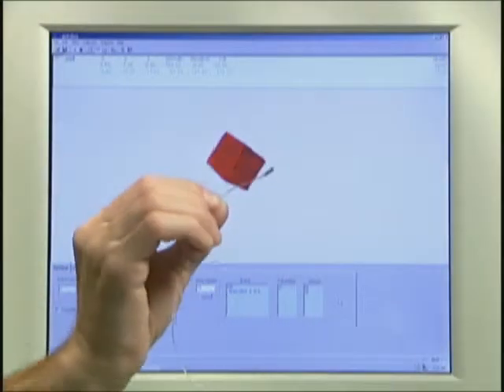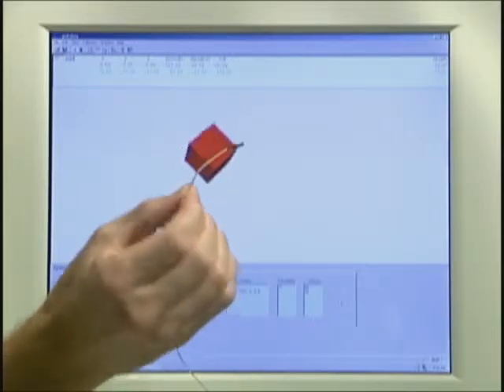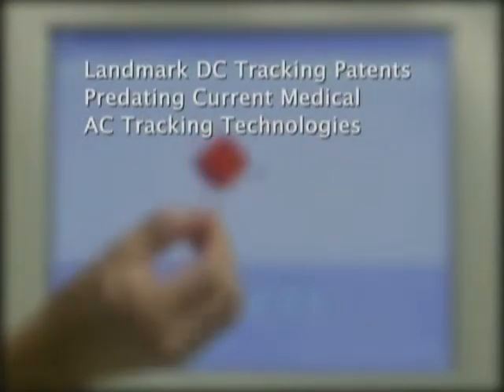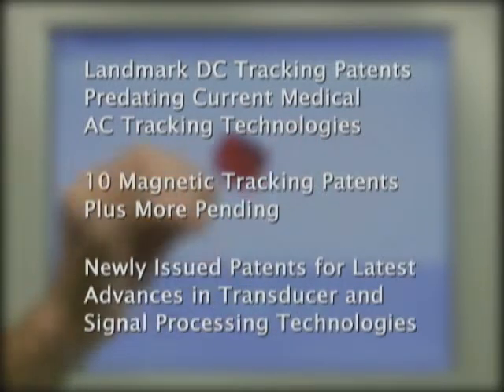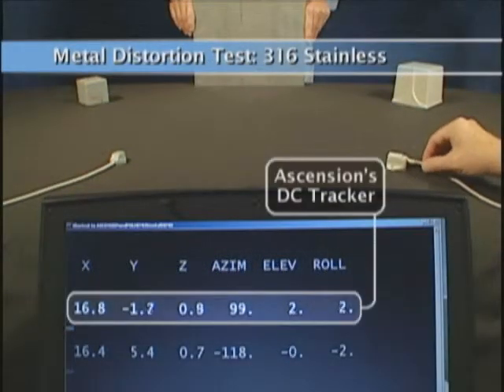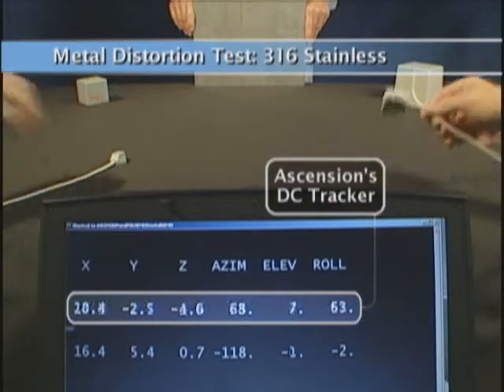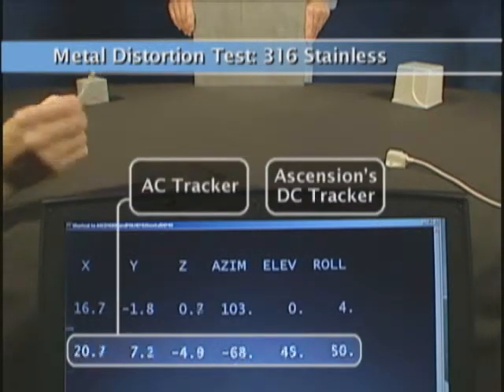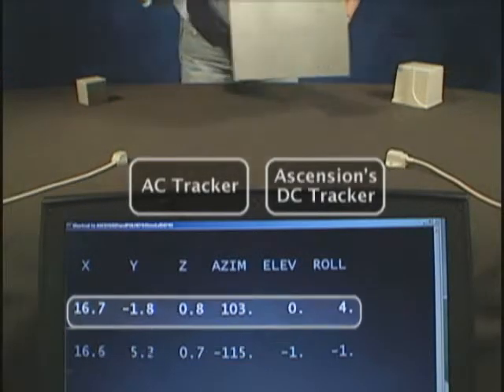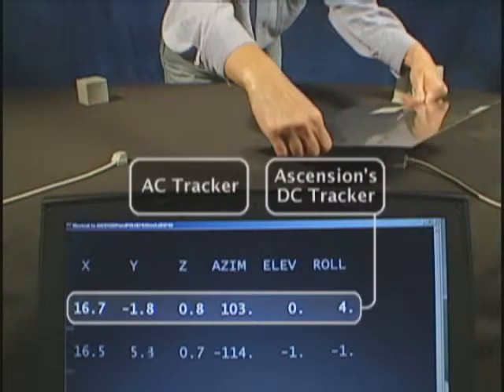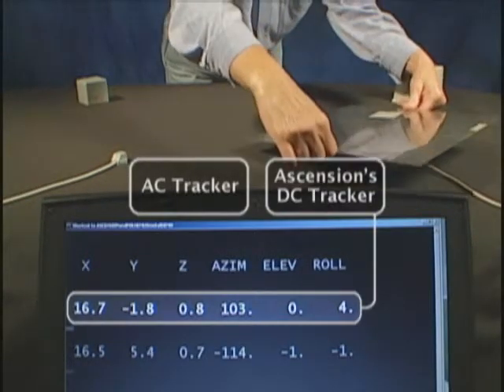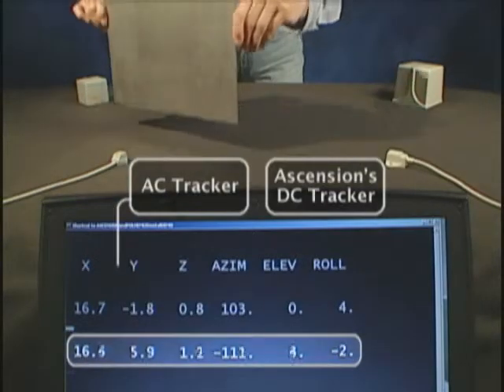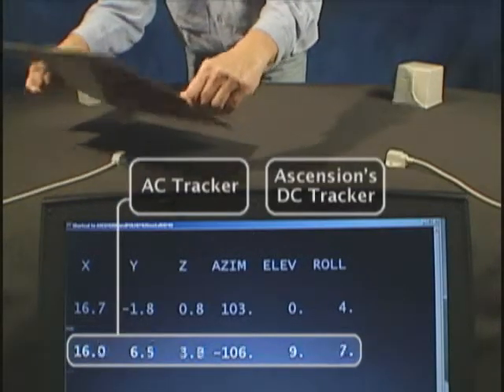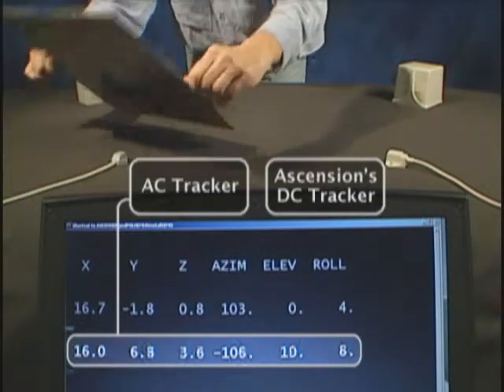Today, our 3rd-generation DC tracking technology represents the state-of-the-art in tracking medical instruments. Besides holding landmark proprietary status, it precedes and leapfrogs competitive AC magnetic tracking technologies in speed, accuracy, and immunity to distortions. DC tracking technology offers superior results when compared to AC electromagnetic systems. First developed in the 1970s, AC tracking systems continuously generate eddy currents in nearby metals. These AC effects distort the accuracy of measurements and cannot be compensated for in real time. In general, DC trackers exhibit 1/5 the sensitivity to nearby conductive metals as AC systems.